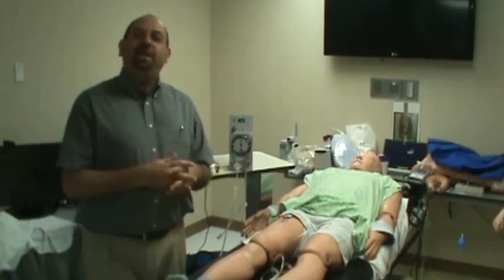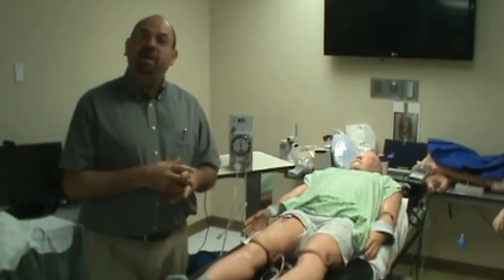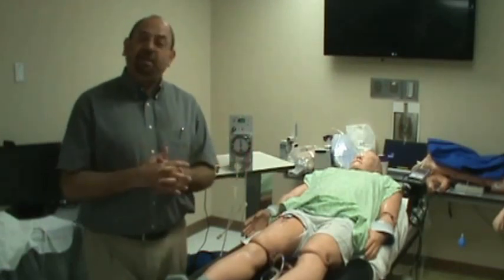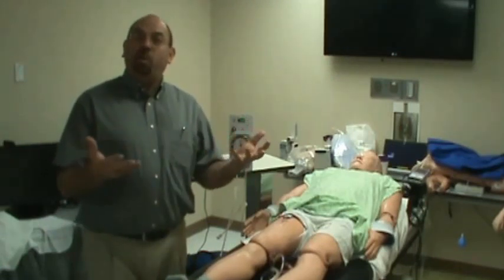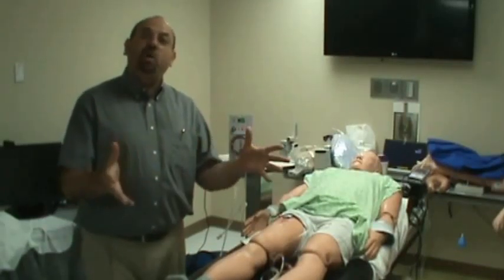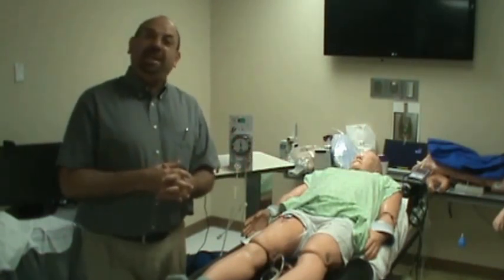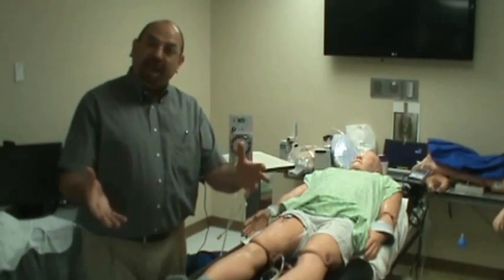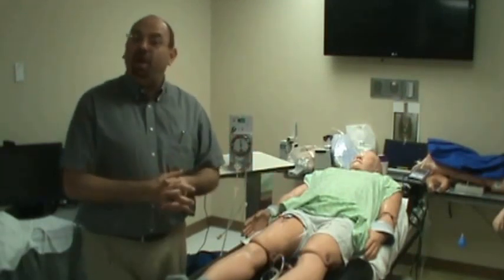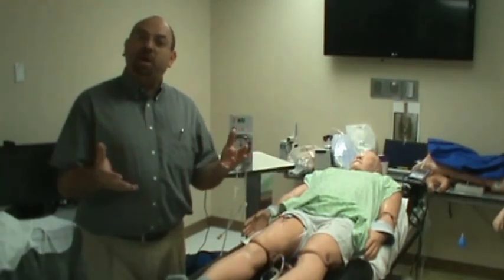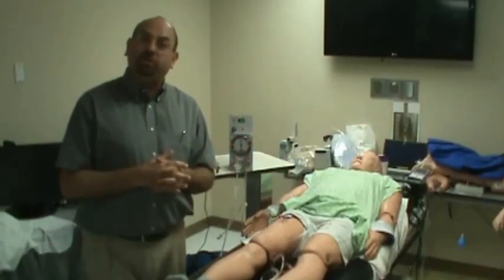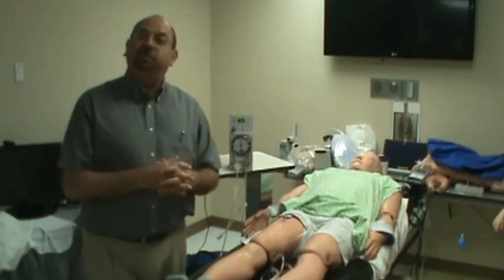you're talking about the need for serious infrastructure. This is a dialysis machine that requires a lot of testing and requires a lot of technical knowledge. You're going to have either a nurse or a technician who knows how to operate the machine and knows how to set it up. Setting up the machine is not easy as well. You have to have dialysate, you have to have different fluids, and you have to have reverse osmosis for appropriate water treatment to be used in dialysis.